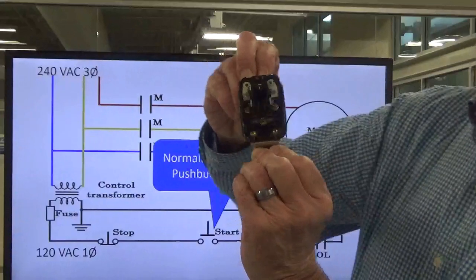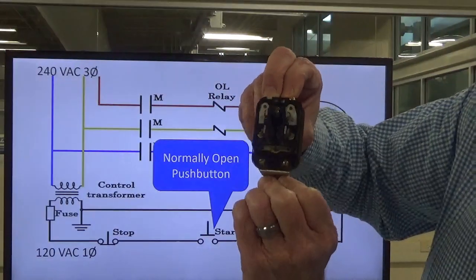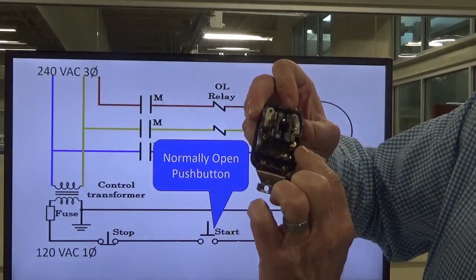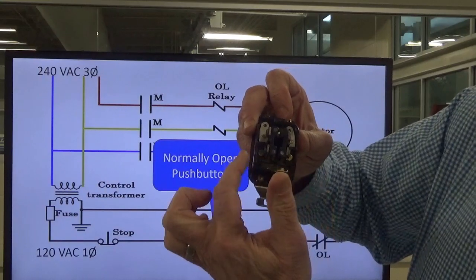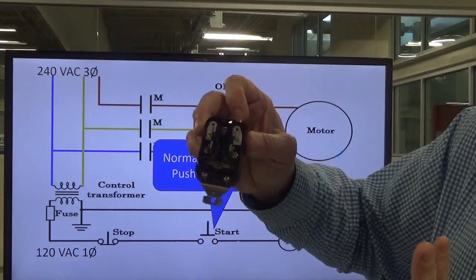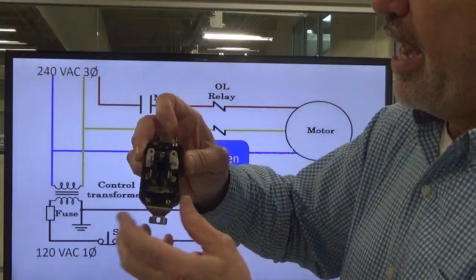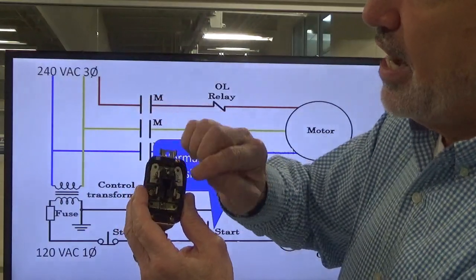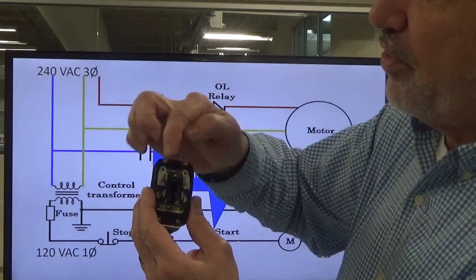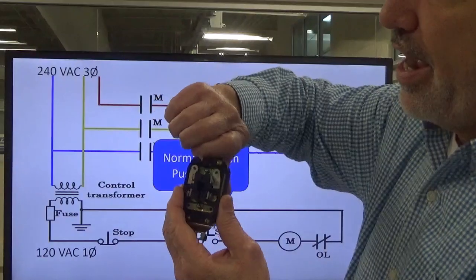You can see that when I press the stop button, these are normally closed, meaning power will go from here to here just by sitting here holding the switch. And this is the normally open set - power can be right here, but it will not flow to the other side until I press the operator.